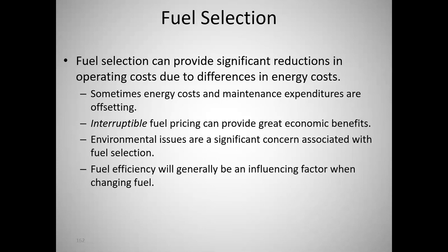But nonetheless, if you have a backup fuel, you can get interruptible pricing, which is someplace between 10 and 20% savings on your whole gas bill. And they don't call many interruptions. Y'all remember the polar vortex when it came roaring through a number of years ago? It was so cold. Up until the polar vortex, nobody could remember when they had called interruptions in gas and electricity.